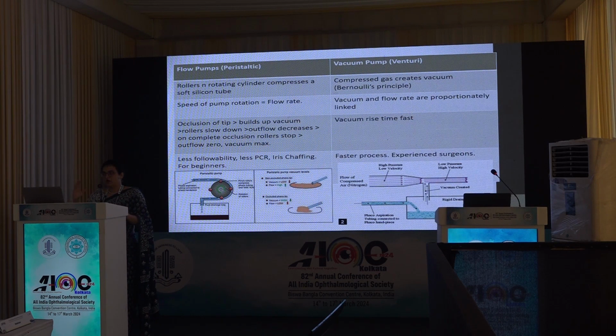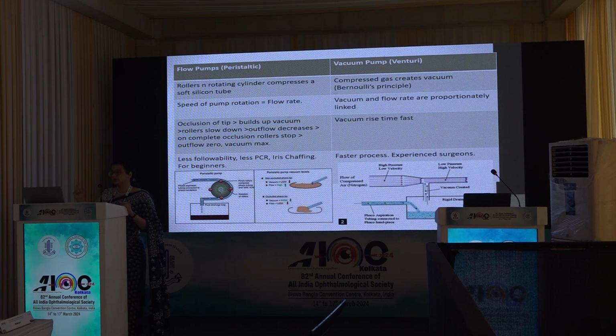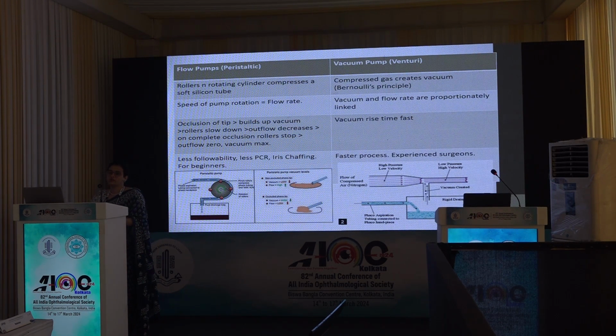so it is better for beginners. On the other hand, we have Venturi pumps, which are vacuum based pumps. They depend on compressed gas, there is a gas cylinder which is compressed and generates the vacuum, based on Bernoulli's principle. Here the vacuum and flow rate are proportionately linked. Vacuum rise time is fast, the process is faster, so it is better in the hands of experienced surgeons.